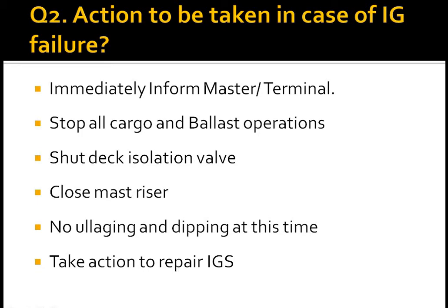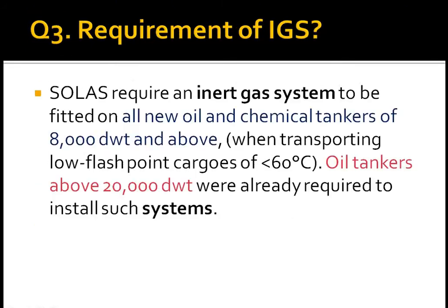Question 2: actions to be taken in case of IG failure. First, immediately inform the master or terminal. Second, stop all cargo and ballast operations. Third, shut the deck isolation valve. Fourth, close mast riser. Fifth, no ullaging and dipping at this time. Sixth, take action to repair the inert gas system.